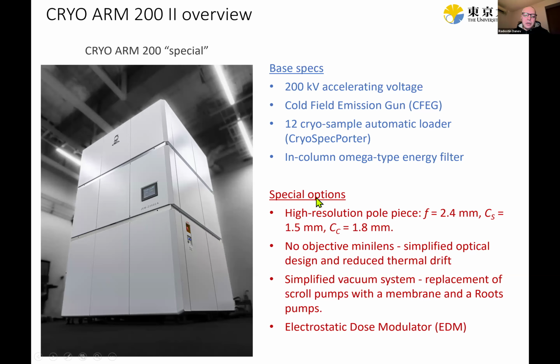And then we requested a high resolution objective lens pole piece. It has a narrow gap and also lower spherical and chromatic aberrations as shown here. The standard values are 2.7 for the spherical and 2.8 for the chromatic. So you see these are lower values, so better optical performance. We also asked JEOL to remove the objective mini lens. This is a lens which they traditionally had in the bore of the objective lens and was used for low magnification observation, but it caused a lot of thermal drift. So switching between low mag and high mag caused a lot of drift.